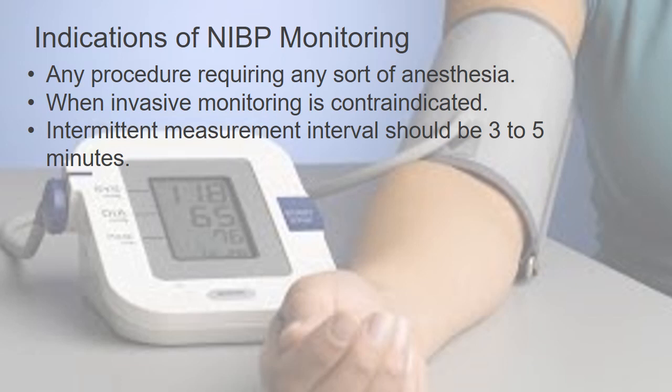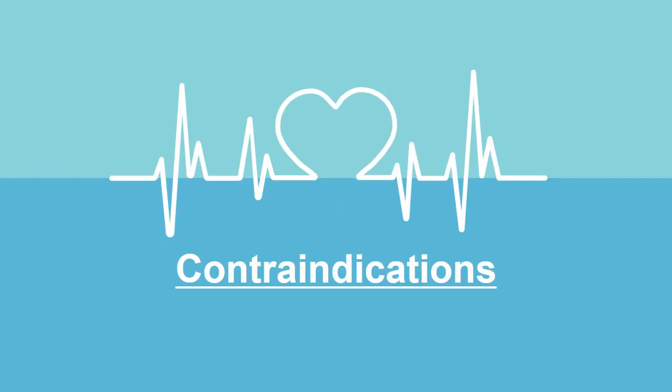The good thing about the automated non-invasive blood pressure technique is that it frees the hand of the anesthetist. I mean, I don't have to do the palpatory or the auscultatory method every 3 to 5 minutes in the OR because I have got an automated non-invasive blood pressure monitoring device. Go ahead and look at the contraindications of these devices.